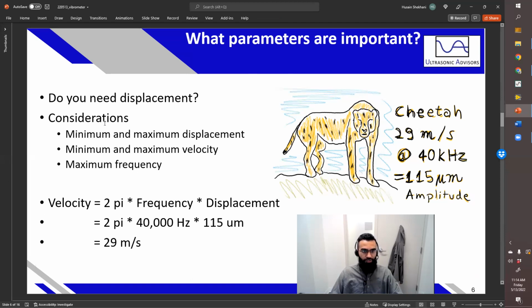Once you determine whether you need velocity or displacement, you need to understand if you want the minimum or maximum. What's the minimum velocity you want to measure? What's the maximum displacement? Those ranges are very important. Some measurement techniques can't measure very low displacement, and some can't measure very high displacement or velocity. You also have to understand the maximum frequency you're going to be interested in.